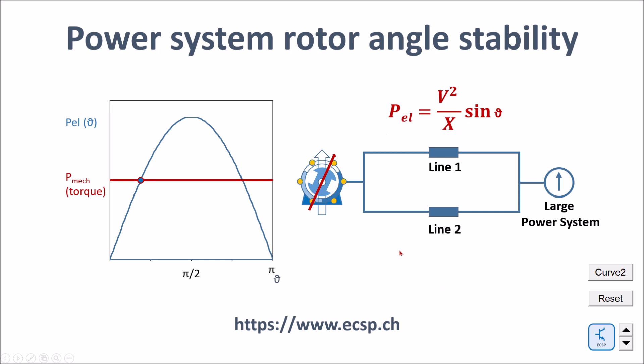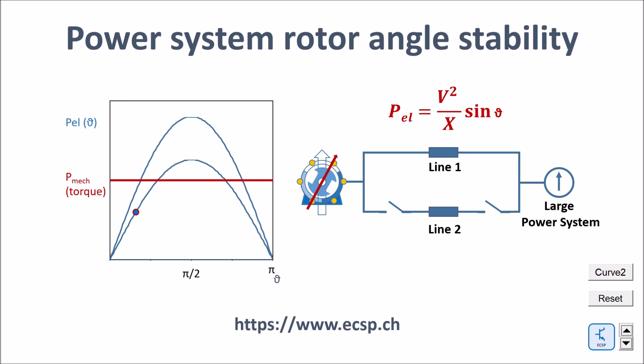Here is another example: a generator delivering power to the grid by means of two lines in parallel. The formula still applies as we have seen before. Due to a lightning strike, I will now lose one of the lines. With only one line, the power which can be delivered by the same generator is less than before. This x is now not the sum of two parallel lines but only one line, so it has nearly doubled. The total electric power which can be delivered is close to 50% of before, and therefore this power curve has jumped down.